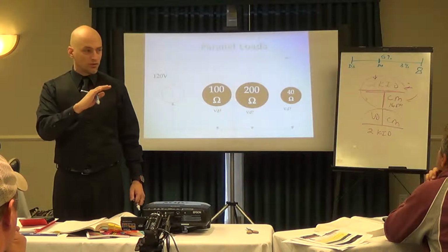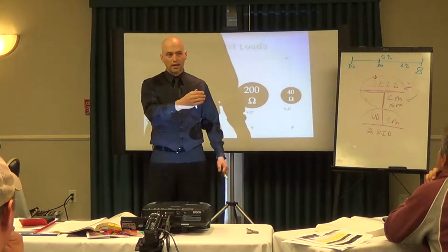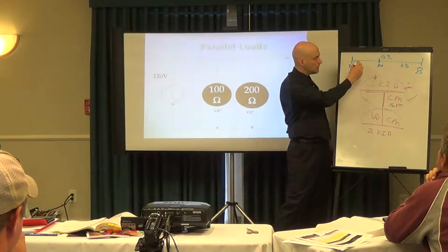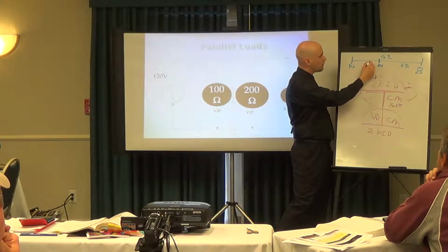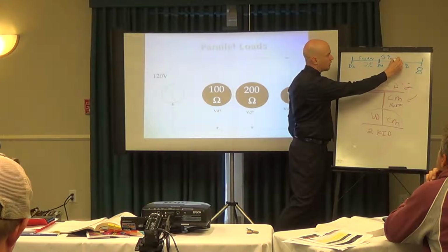If I've got two breakers involved, then it's feeder and branch circuit. If I've just got from breaker to breaker, then I've got feeder. And so mathematically, they don't tell you this in the code book, but it goes to say that that's 3% and that's a max 5%, this is going to be 2%. So this is feeder, this is branch circuit.